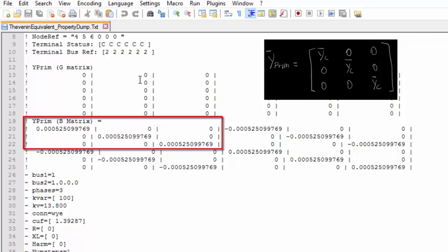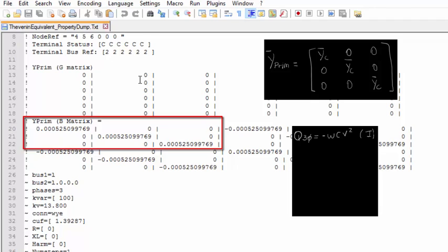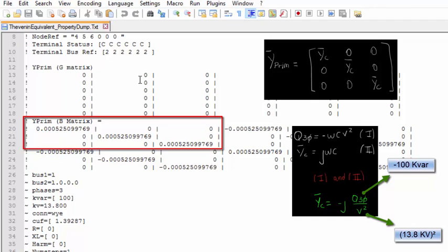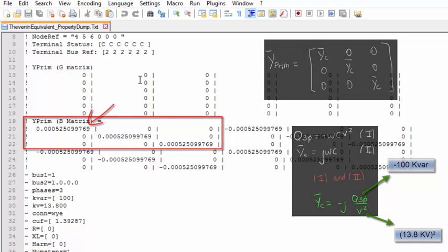We can also verify the value of Yc by using the expression we derived at the beginning of this example. We know that Yc is equal to J omega C. Then, we can say that Yc is equal to minus J times the three-phase reactive power divided by the square of the rated line-to-line voltage. Pay attention that the value defined in the KVAR parameter is the rated reactive power of the element, which means the module of the reactive power. We know that the actual reactive power consumed by a capacitor has a negative sign, because it is generated, not consumed. Then, we have that Yc should be equal to minus J times minus 100 kVAR divided by 13.8 kV squared, that is J 0.000525099769, exactly the same value calculated by OpenDSS. Keep in mind that the B-matrix does include the J, because it is already the imaginary part of Y.